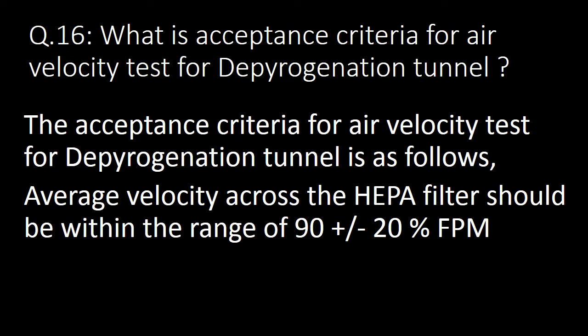Next important question: what is the acceptance criteria for air velocity test for depyrogenation tunnel? The acceptance criteria for air velocity test is as follows: average velocity across the HEPA filter should be within the range of 90 plus or minus 20% of fpm, that is feet per minute.